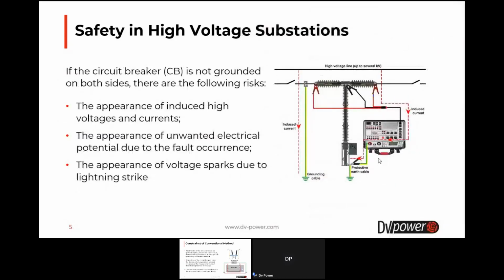If the circuit breaker is not grounded on both sides, there are the following risks: the appearance of induced high voltages and currents from adjacent energized conductors, the appearance of an unwanted electrical potential due to fault occurrence, and the appearance of voltage sparks due to lightning strikes. These dangerous voltages can be transferred to the device by the test leads and can threaten testing personnel who are in contact with the test device.